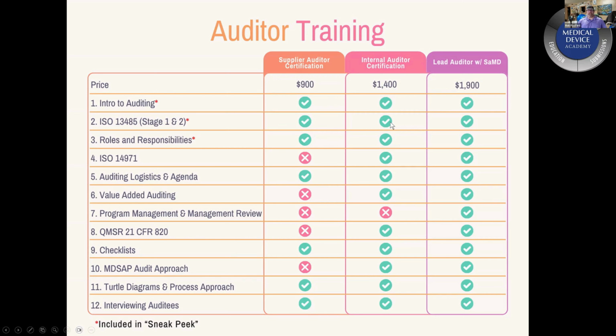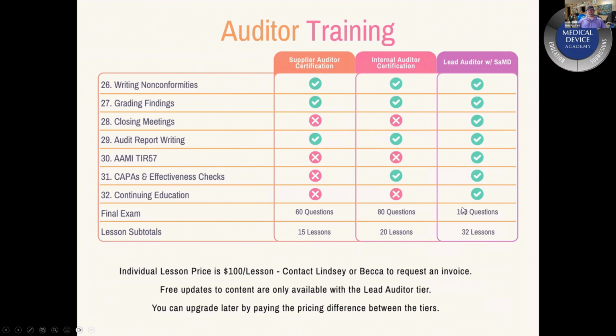Yeah, okay. Well, I guess computer system validation. So I think what we're talking about there is software tools for the quality system, not software as a medical device. If that's what they mean, there's a different standard you should use. Everybody talks about 62304, but there's actually a more useful standard from a risk management standpoint called IEC 80002-1 that tells you how to apply risk management to software. But then they have a separate one with a similar number, 80002-2, for software that's used for the quality system. In the very back of that standard, they give you examples of how to validate a spreadsheet, how to validate a molding machine, how to validate production equipment. So for any kind of quality system software, they give you examples of how to do those software tool validations.